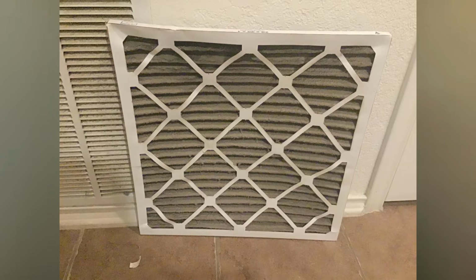So when dealing with ductwork that's 30, 40, 50 years old, you have to keep this in mind. So when it comes to something like metal ductwork, this is going to be the main factor on its life expectancy. And that's because metal ductwork is hard to modify. So it might have a super long life, but it's still subject to technology and comfort standards. The next thing is, how do you keep your ductwork as clean as possible? Well, you're going to want to make sure that your ductwork stays sealed, especially on the return side, along with routinely changing your filters. Because we don't want dust and dirt continuously being ran through your ducts, because at some point it's going to make your ducts so gross that you're probably just going to want to replace them.